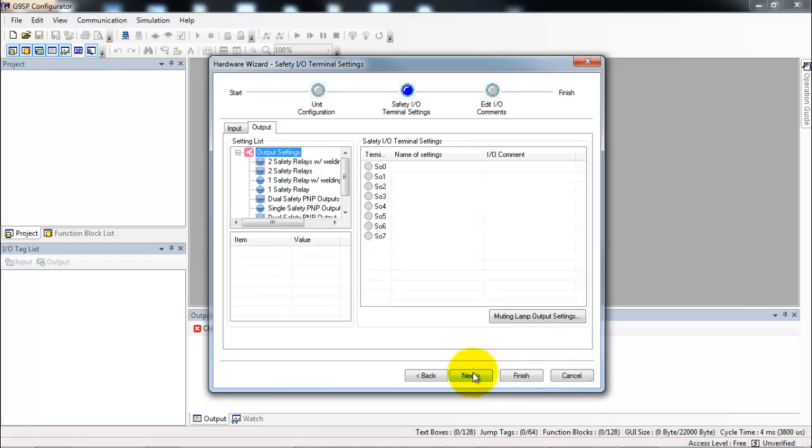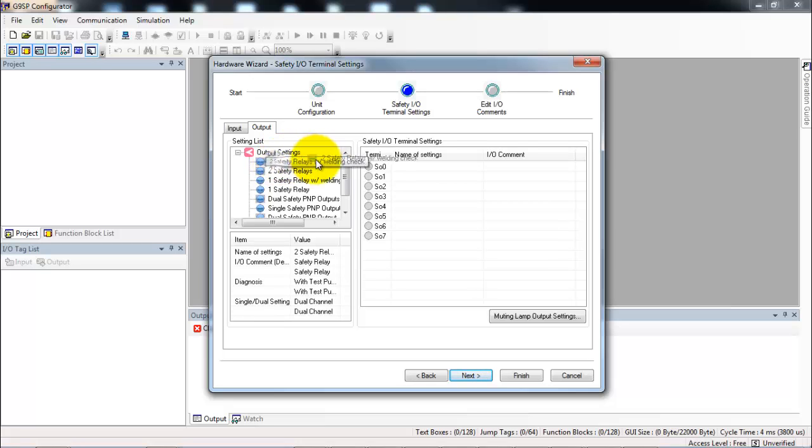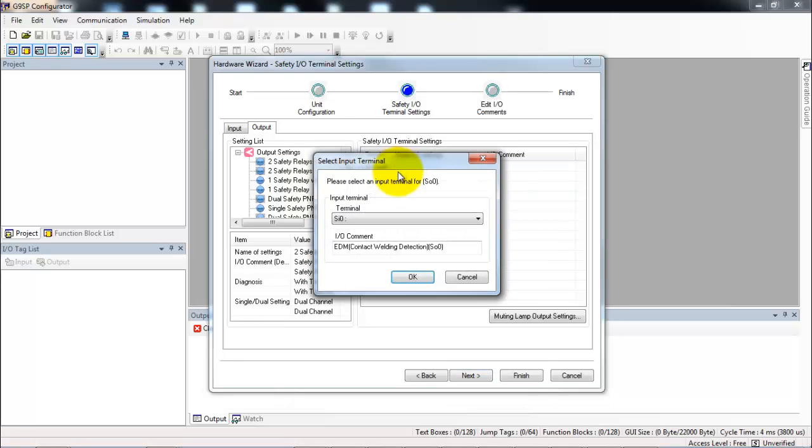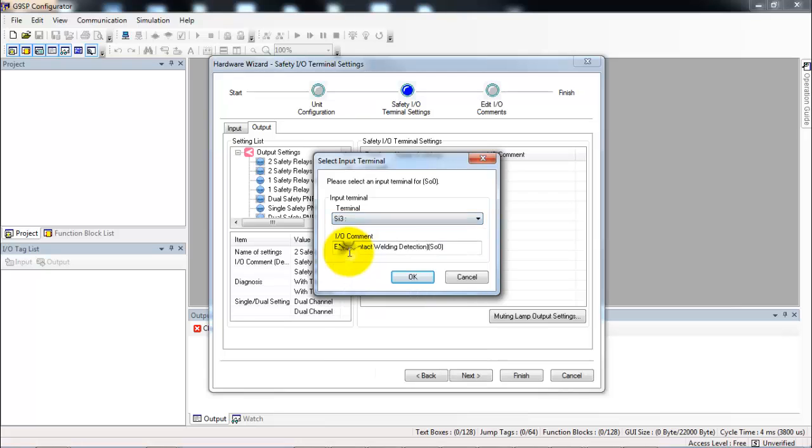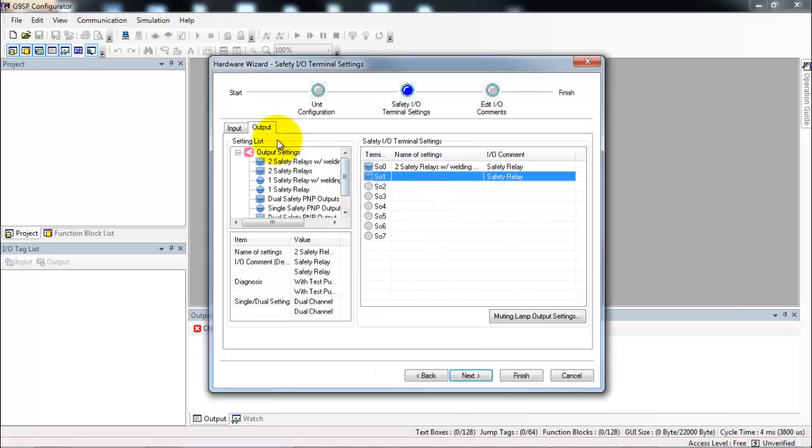Next I configure my IO. We start with the outputs. I have the two force-guided relays and the external device monitoring signal for the welding check. So I'm going to grab this first option here and drag it over top of the first two outputs. Since the welding check will also require an input, it asks us which input to wire into, and I'm going to tell it that I used safety input 3.